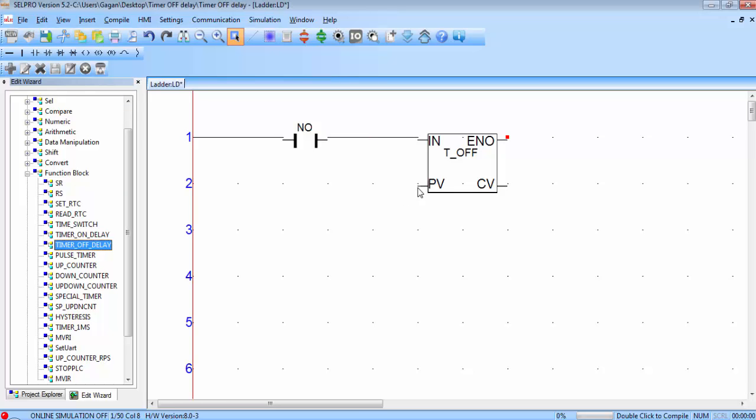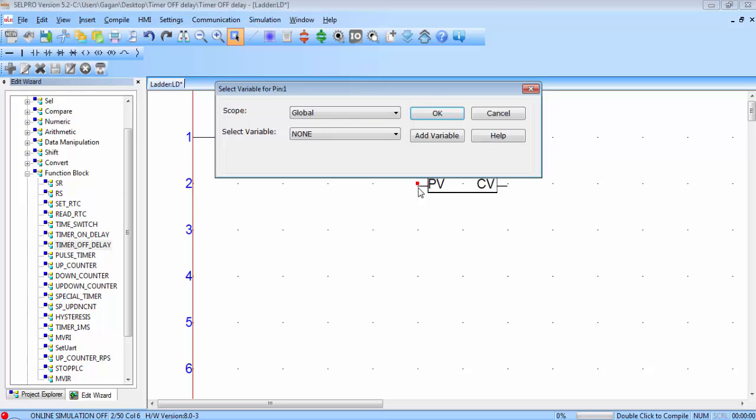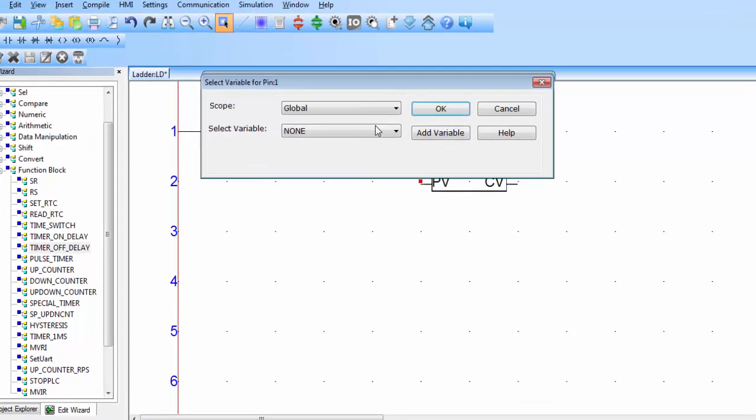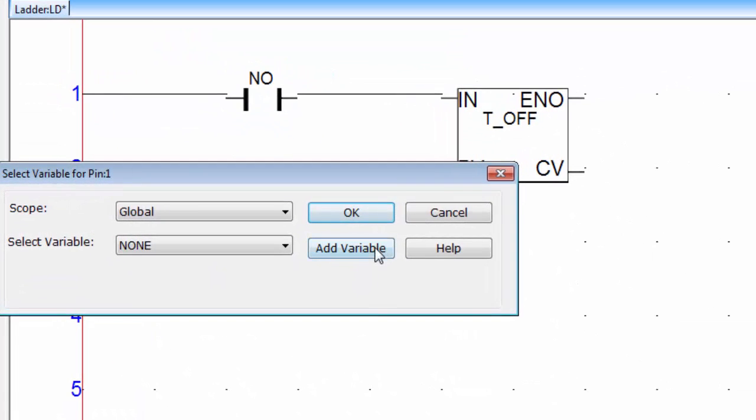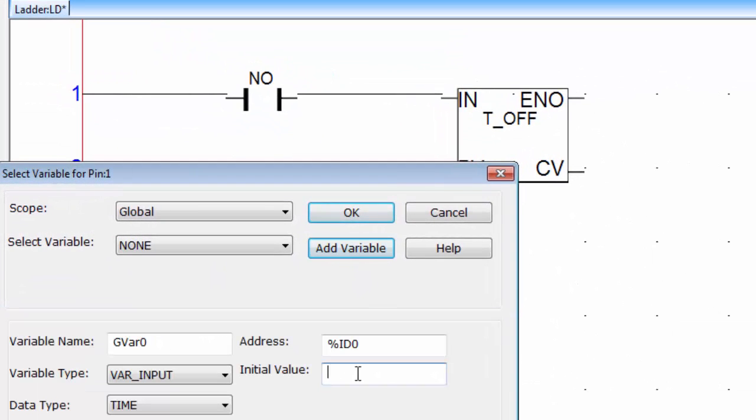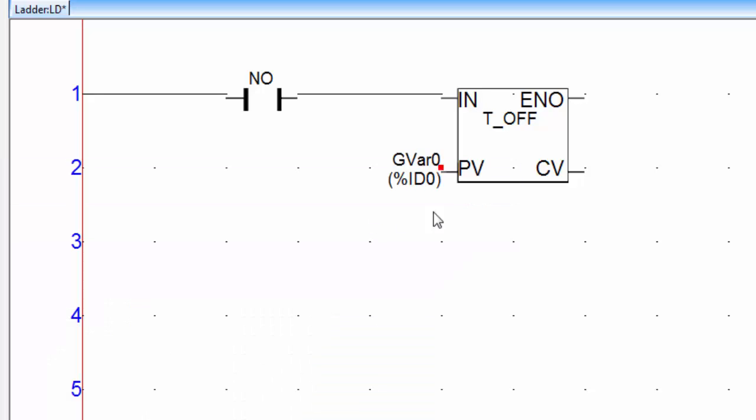Double click on the PV which is the preset value of the timer. Click on Add variable. The initial value of this variable is the time required for the application. Suppose I need 3 seconds. So type T#3s for 3 seconds. Click OK. PV value is assigned.